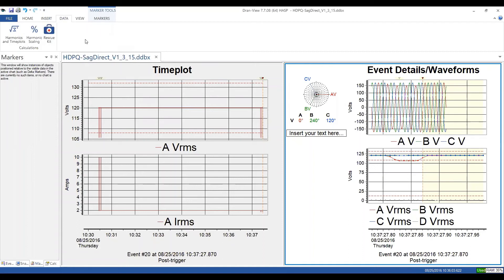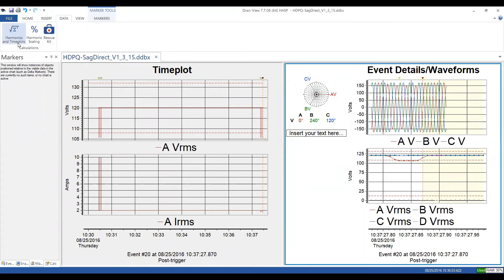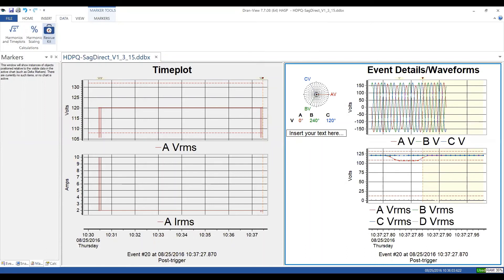The Data tab has more advanced topics we'll cover another time. This includes the harmonics and time plot calculator, mostly available in DRANview Enterprise. For example, if you want to recompute harmonics from your waveforms because you didn't store harmonics in your survey, you can do that here, along with recomputing other parameters. You can also scale harmonics. And there's the Rescue Kit — covered in a future web meeting — for changing CT scale factors, inverting CTs, and similar tasks.